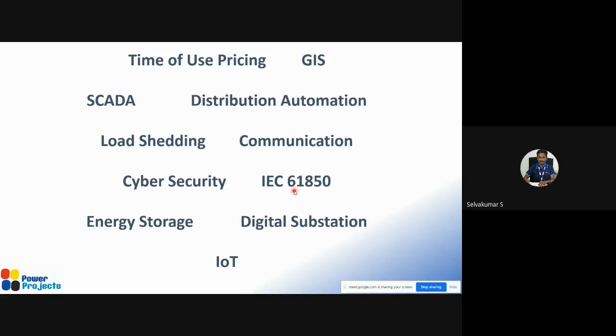Given the freedom to choose different vendors and still have the same sophistication of communicating, based on the IEC 61850 protocol, everything is standardized. The manufacturer has to comply with this. That means tomorrow, if I want to replace a GE relay with a Siemens relay, that is easily possible. So that's basically IEC 61850.